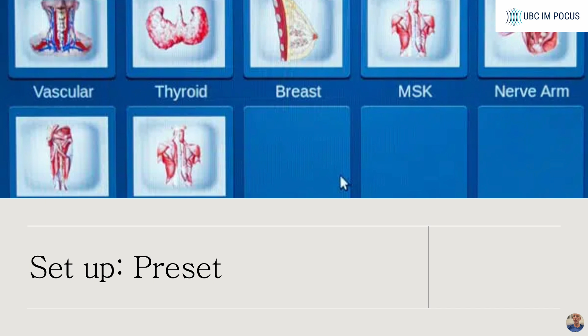You should have a basic understanding of the probe qualities to inform this decision. First, the curvilinear array transducer. It can be seen here on the far left of the image. It is a low-frequency transducer providing good depth of penetration. It has superior spatial resolution when compared to other common low-frequency transducer, the phased array. However, the spatial resolution is not as good as a high-frequency probe such as the linear array. It has a large footprint, providing comfortable contact and delivering a large field of view. It is excellent for scanning the abdomen and chest.